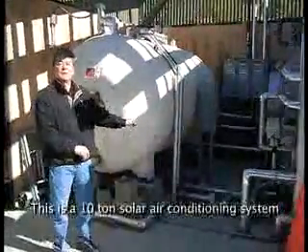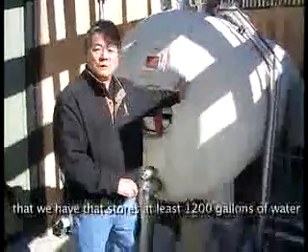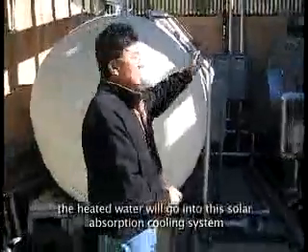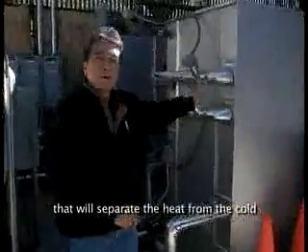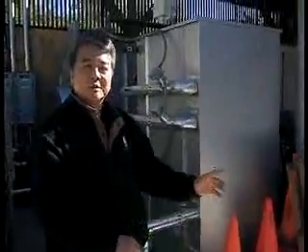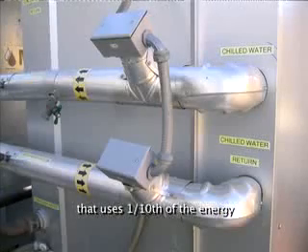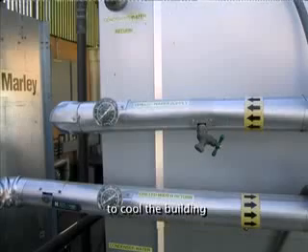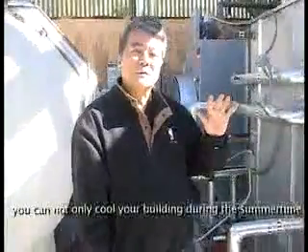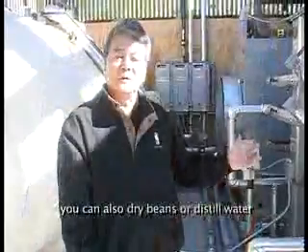This is a 10-ton solar air conditioning system that stores at least 500 gallons of water in this tank, heated up to 200 degrees Fahrenheit. The heated water goes into this absorption cooling system that separates the heat from the cold and creates chilled water for the air conditioning system. This absorption chiller is a 10-ton Yazaki absorption chiller system that uses one-tenth of the energy to cool the building. In a remote stand-alone setup, you can not only cool your building during the summertime but also heat it during the winter, and dry beans or distill water or desalinate.